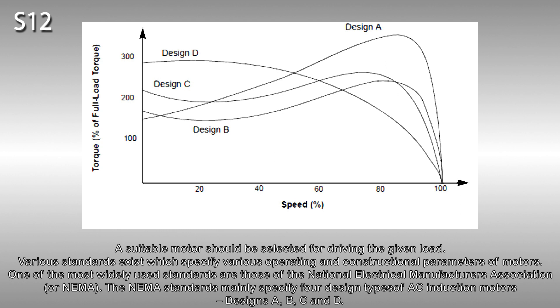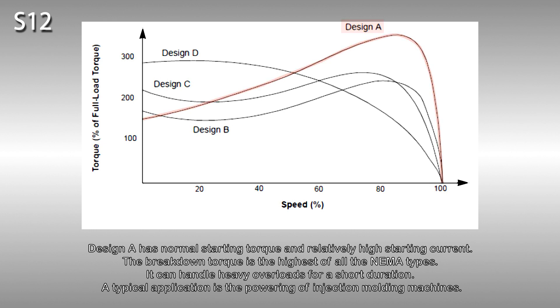A suitable motor should be selected for driving the given load. There are various standards which specify various operating and constructional parameters of motors. One of the most widely used standards are those of the National Electrical Manufacturers Association or NEMA. The NEMA standards mainly specify four design types of AC induction motors, designs A, B, C and D. Design A has normal starting torque and relatively high starting current. The breakdown torque is the highest of all the NEMA types. It can handle heavy overloads for a short duration. A typical application is the powering of injection molding machines.